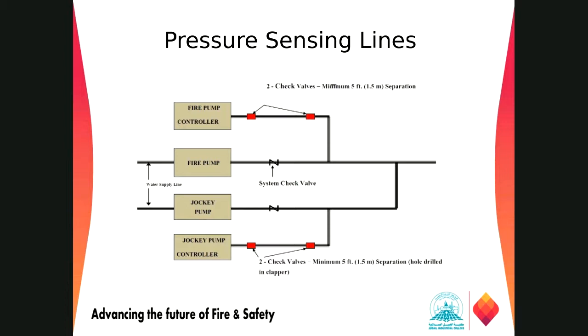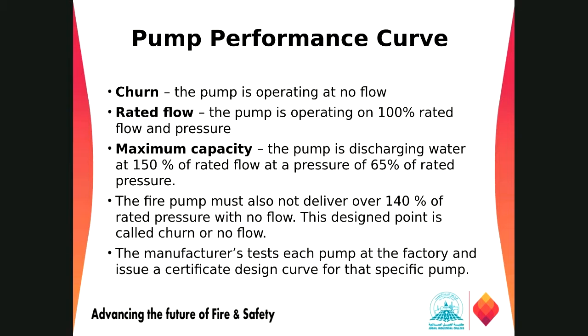Look for the number of check valves, right? We need 2 check valves facing the same side in each fire pump sensing line, and there should be separate sensing lines for all the controllers, right? So we cannot take one sensing line for all controllers, the one we discussed in fire protection design.